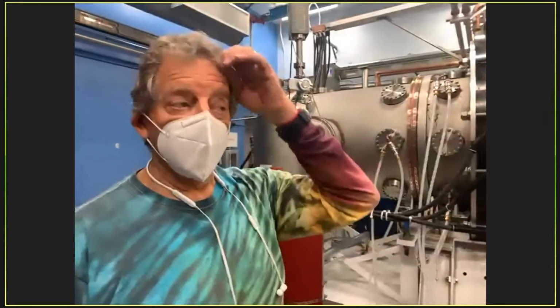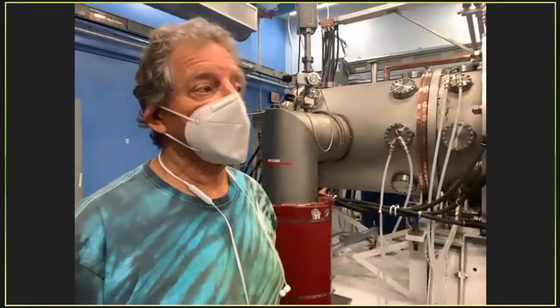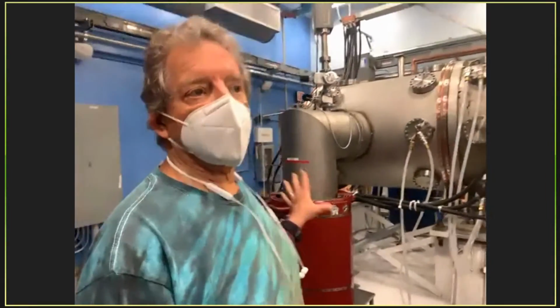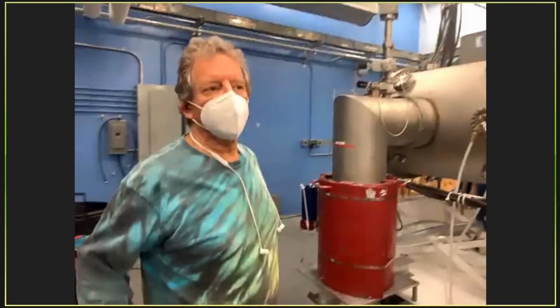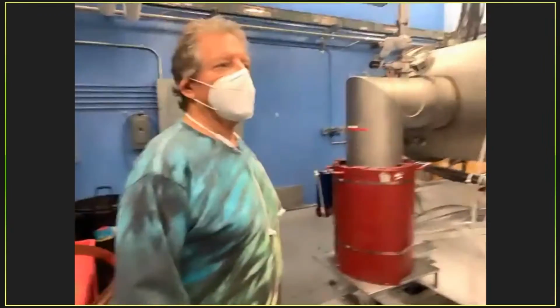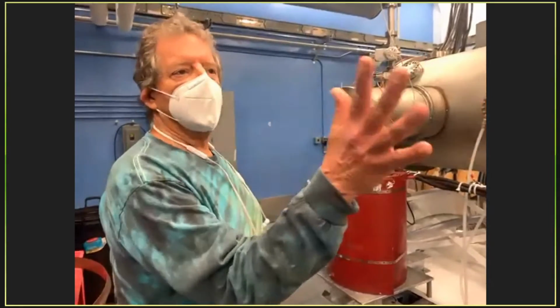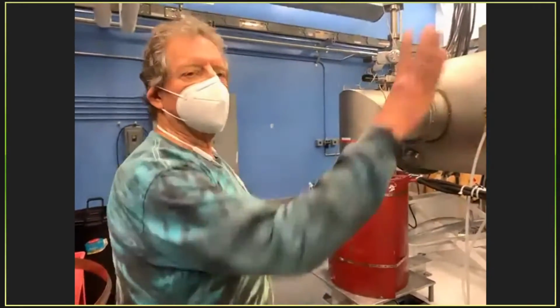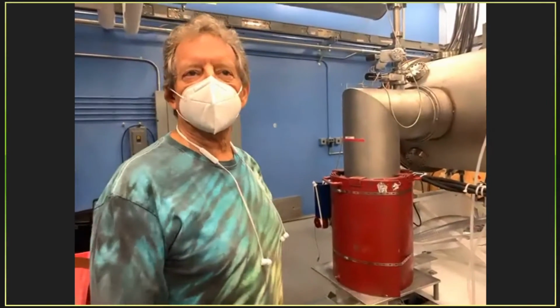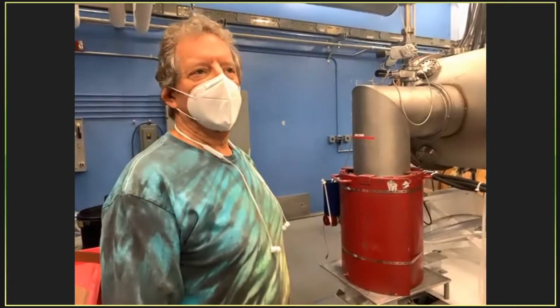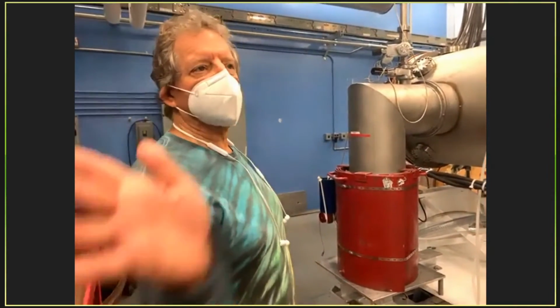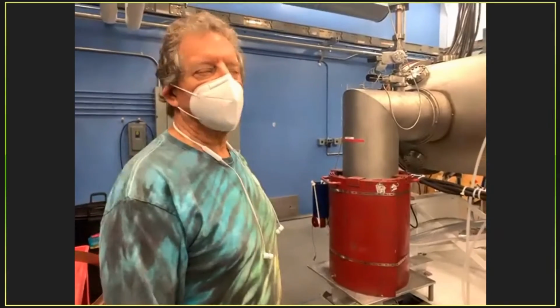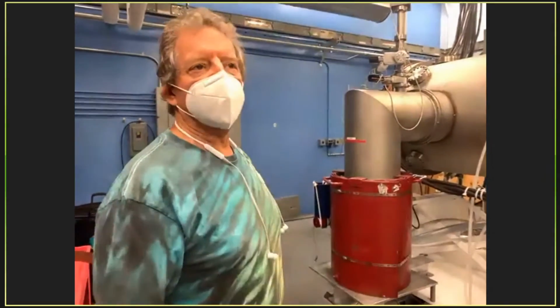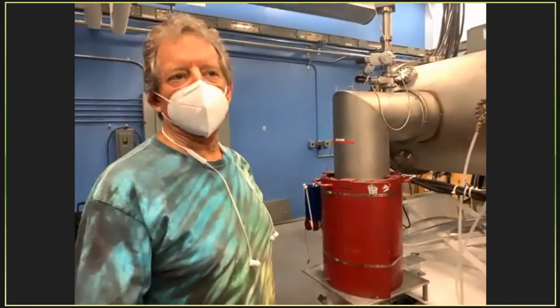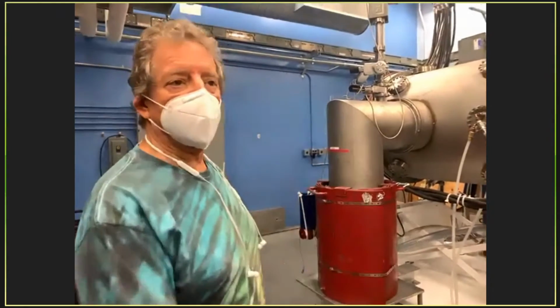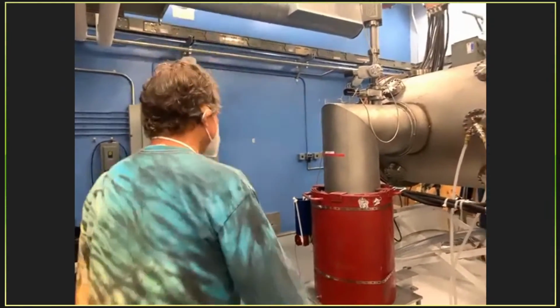So first we have to pump all the air out of the machine. The pumps must be on day and night. They can never shut off. The reason is that at these very low pressures, the walls and the probes and everything are evaporating all the time. There's no liquid state. They just evaporate and become gas. And that will make the vacuum contaminated and useless to make plasma in. So we're always pumping the machine.